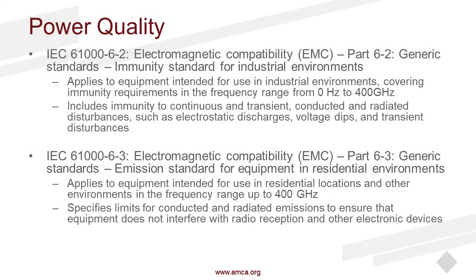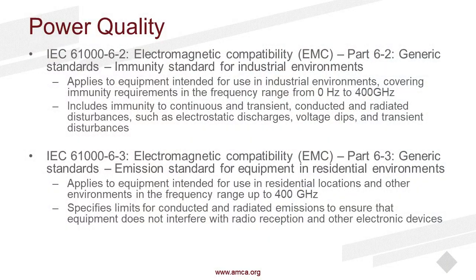So we're looking at IEC 61000-6-2. This is for your industrial environments. Immunity is where it's saying it wants to prevent that any other equipment, anything else on your grid is affecting this device or this equipment. It's looking at ranges from 0 hertz to 400 gigahertz. And it's still looking at your power quality, making sure that you're looking at your transients, your dips, your voltage, and harmonics.